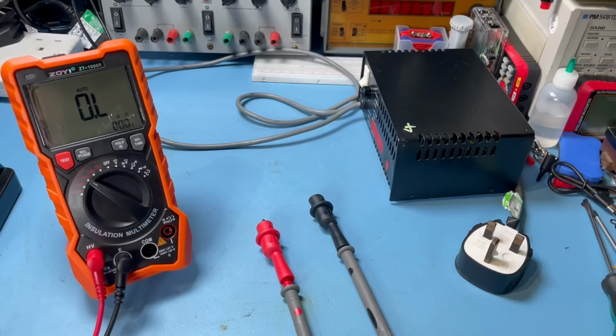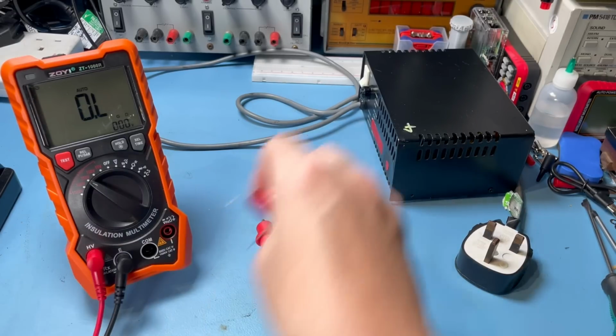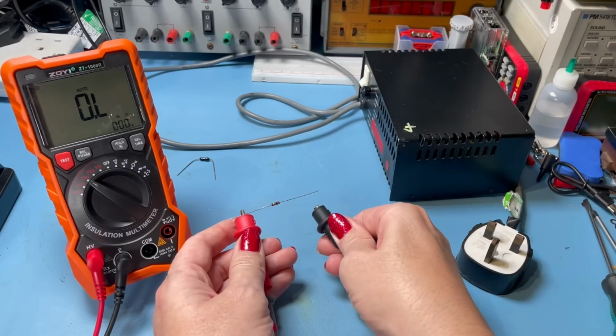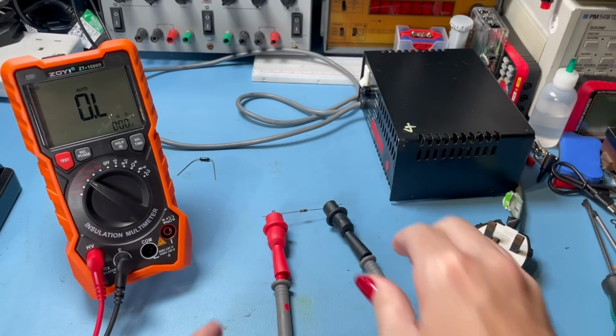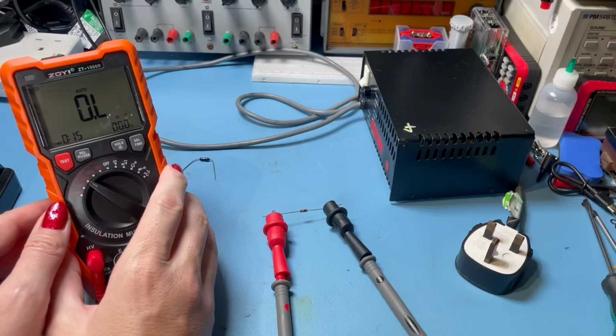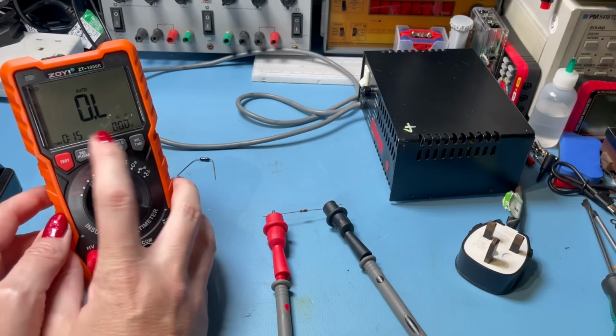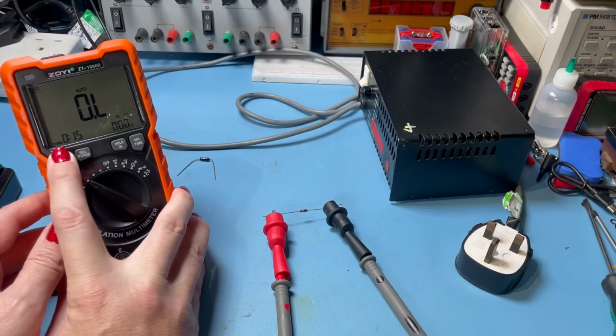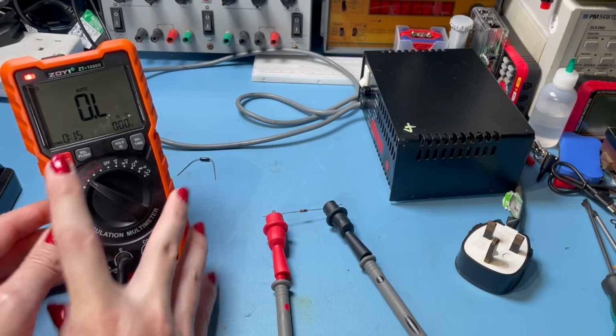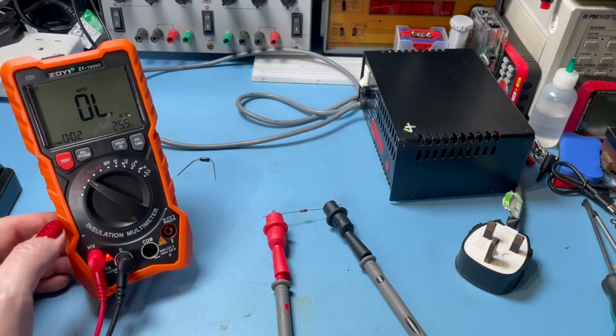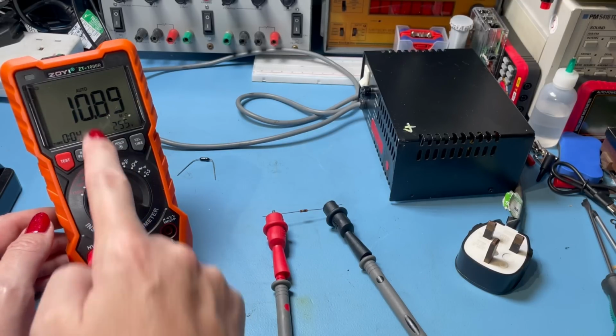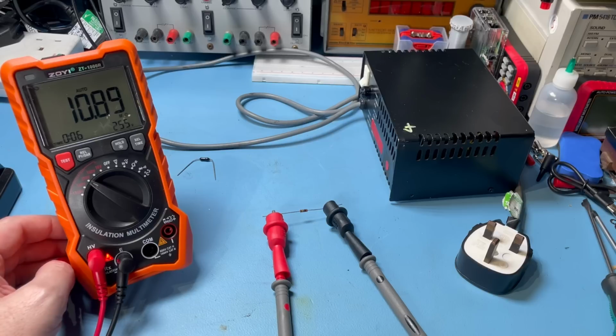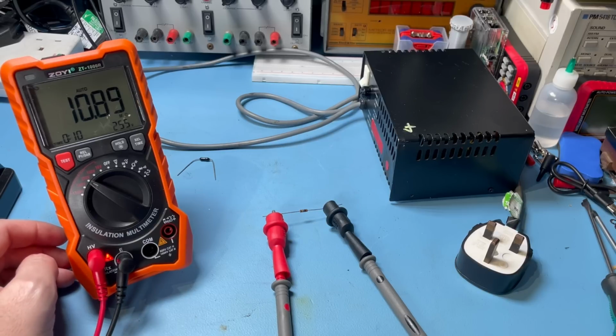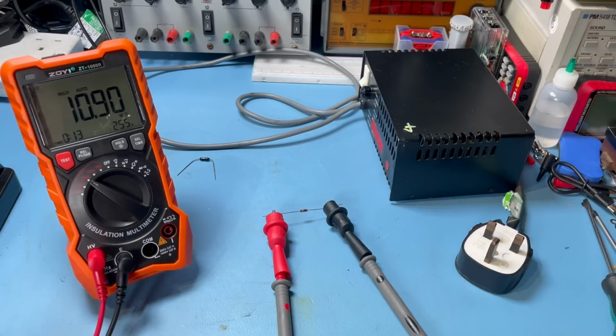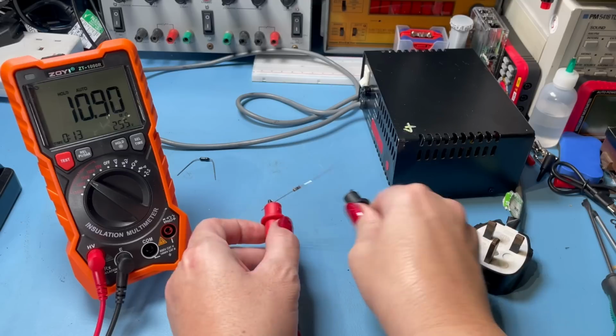Okay, so another thing we could do is check a couple of resistors here. So let's try a 10 meg at 250 volts. We should be all right on that. Now, we don't need a DAR test on this. We'll just set the timer for 15 seconds and test on 250 volts. And there we go, yeah, 10.89 megs. That seems pretty solid performance to me. There you go, and you can stop the test because we don't need to test for any length of time.